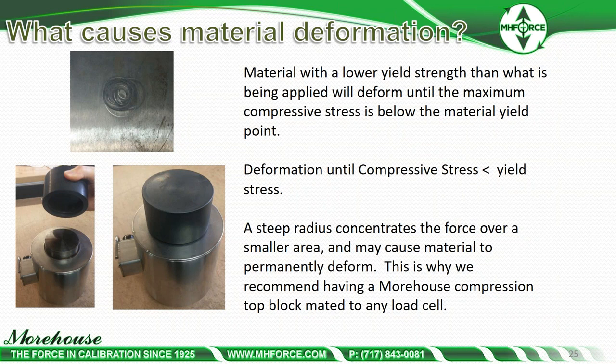We avoid the 0.3% errors and get very good agreement. The customer has the O-ring and can secure it on the cell — it's very repeatable. You get the cell, get it calibrated by us with the block, and you can expect the same performance when you use it in your setup and your machine.